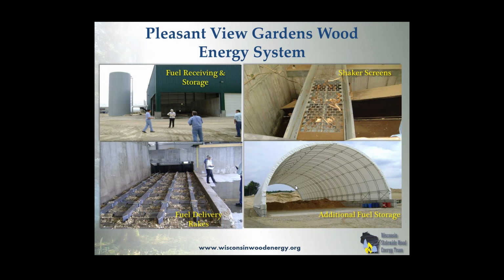And you can see this is a little unique. They built this additional fuel storage in the lower right-hand corner of the picture. It's a hoop barn, and they bring and drop local tree trimmings and cuttings in. Then they have this big open corner to their boiler room and fuel delivery portion. In the lower left-hand corner, you're looking at the fuel rakes. You can dump directly onto them from a bucket loader, or they can drive trucks directly on those rakes and unload them. So this is one place that did take advantage of some low-cost storage because they've got seasonally available product that they can get at a very low cost. They have sorting to accommodate the tree trimmings and other things that come in there. This is in New Hampshire.